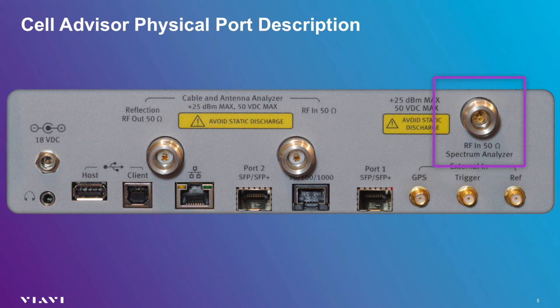It is important to keep in mind that you should never connect this port directly to a device that outputs more than the maximum allowed input for this port, which is 25 dBm, or approximately 300 milliwatts. Be sure to use an attenuator if you suspect the power might exceed 25 dBm.